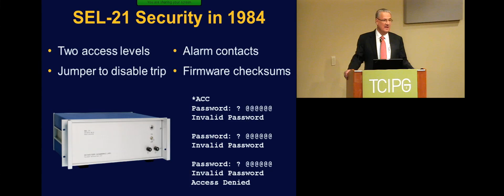So let's take a look at that. Here's the setup. There's your terminal on the left, a modem, a public switch telephone network, or maybe a private network of the utility, another modem in the substation, possibly some other switching stuff, and the digital relay. So as I mentioned, you do the access and the password, get it wrong 3 times, the alarm contact bangs. You connect that alarm contact up to the SCADA system, and now we've got authentication, or at least a notification of a problem, and the next slide will show the way we authenticate.